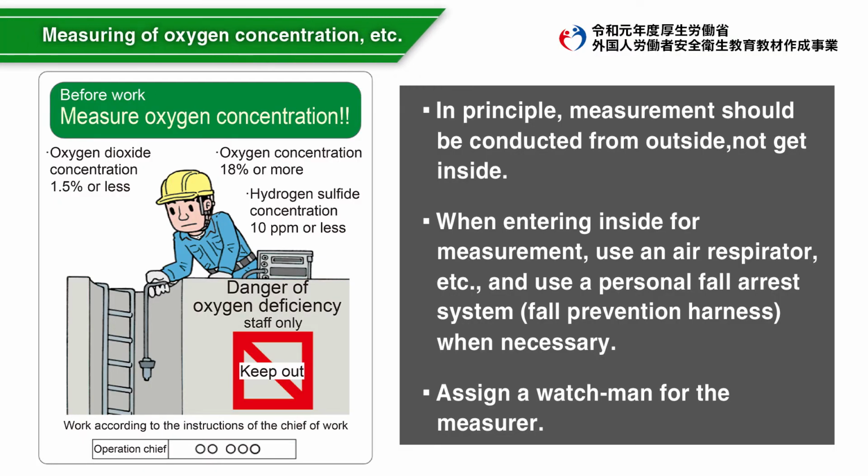An operation chief measures the oxygen in the workplace before starting the work for the day. It is also necessary to measure when all workers leave the workplace after a break, etc., or when they start working again, or when there is an abnormality in the worker's body or a ventilation system, etc. When measuring concentrations, attention should be paid to these points.